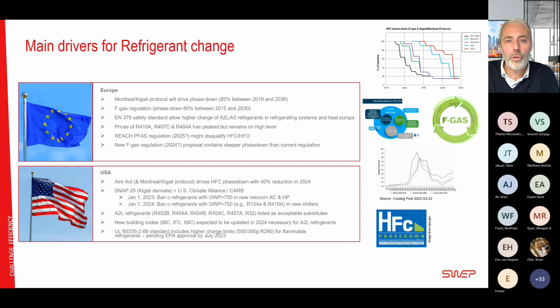Moving on to the refrigerant change and the main drivers. Let's start with Europe. In Europe, we are guided by the Montreal Protocol and the Kigali Amendment, and this will drive a phase down between 2019 and 2036, with a total of 85% phase down. But on top of this, we have the F-gas regulation, which is a more aggressive phase down, at least initially. It will phase down 80% of the emissions between 2015 and 2030.